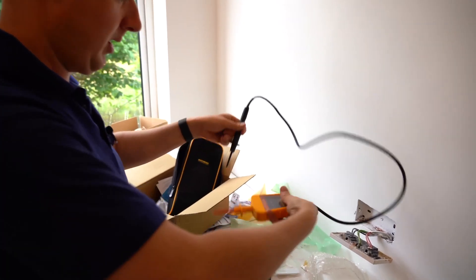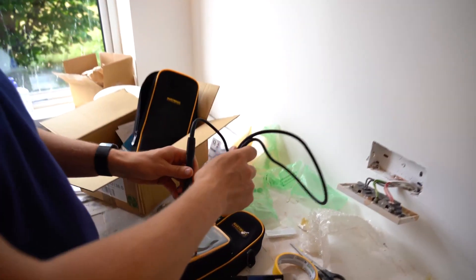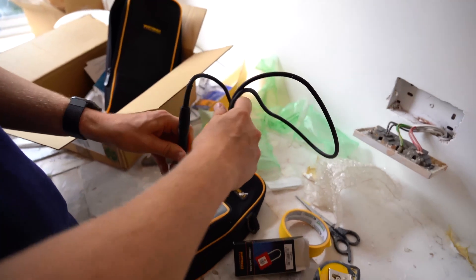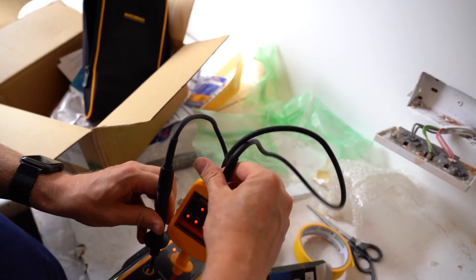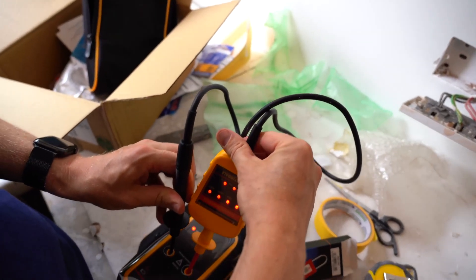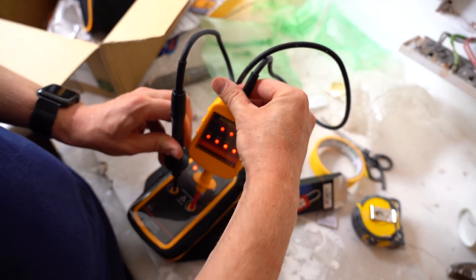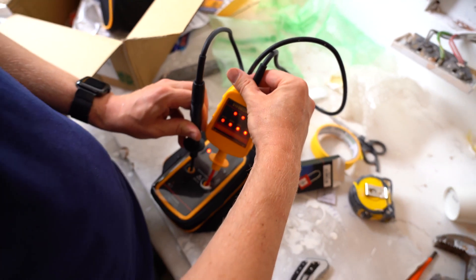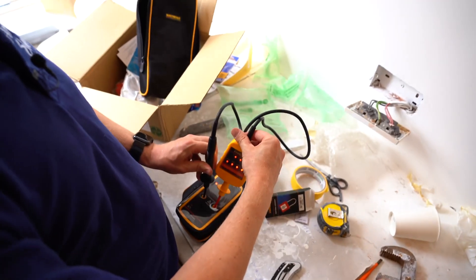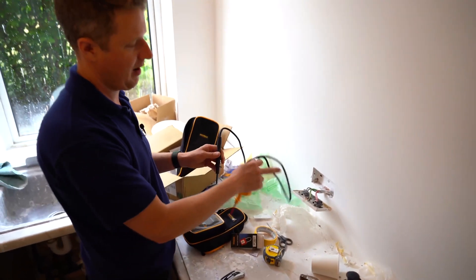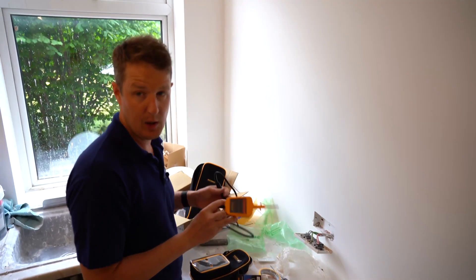We just pop the tester on there and you can see that we've got power, so we know that our tester is working. And we can be confident then that that reading that we took that it was dead, it's actually correct.